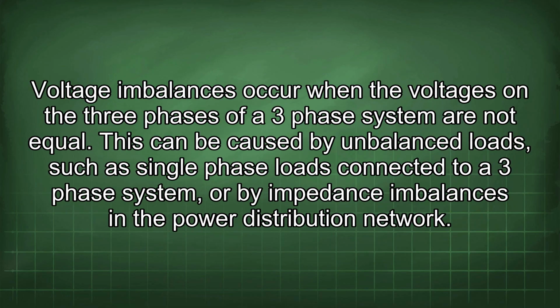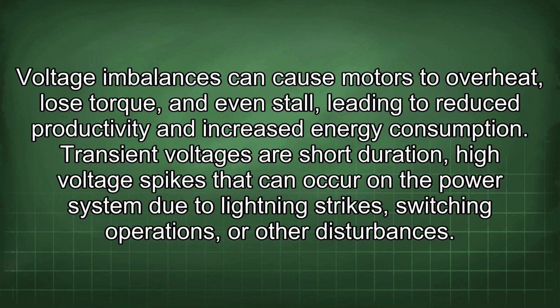Voltage imbalances occur when the voltages in the 3 phases of a 3-phase system are not equal. This can be caused by unbalanced loads, such as single-phase loads connected to a 3-phase system, or by impedance imbalances in the power distribution network. Voltage imbalances can cause motors to overheat, lose torque, and even stall, leading to reduced productivity and increased energy consumption.